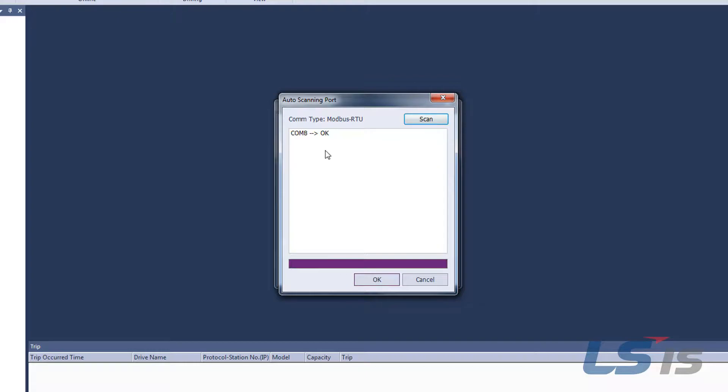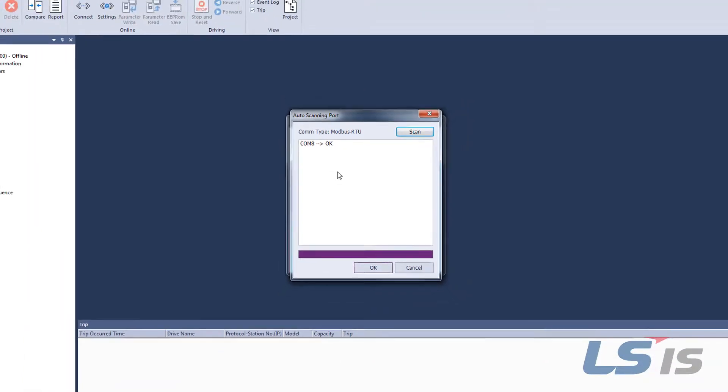This should result in a COM port being listed with OK next to it. If NG, make sure that the driver is installed properly and that the cables are secure. If you still have an issue, confirm again that the baud rate is 19.2 in both DriveView 9 and the device manager.